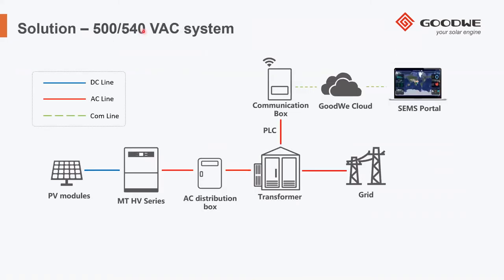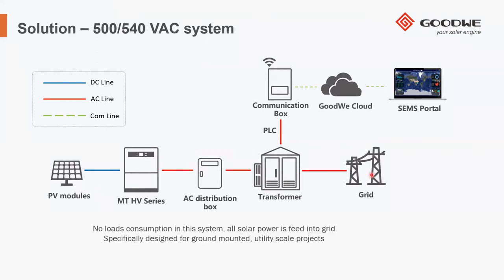For the solution with the exit at 500 or 540 volt AC, typical configuration is with PV modules, the inverter, AC distribution box, a trafo, and the connection to the grid. So this is typically when you have an incentive tariff, so you are paid for the energy that you transfer to the grid. Here, as an example, the monitoring data can be transferred through PLC, which is one of the characteristics of our system, and I will speak later about this.